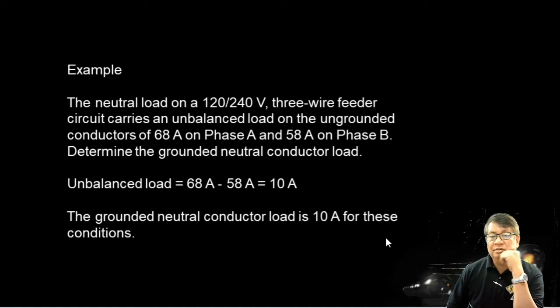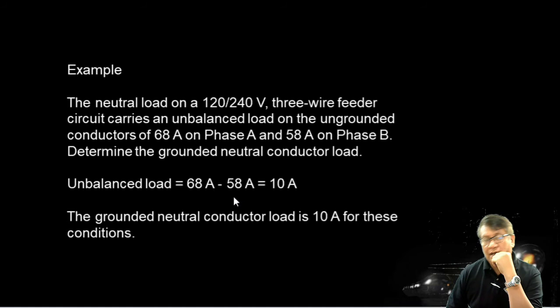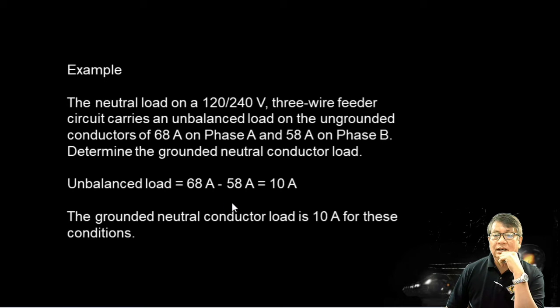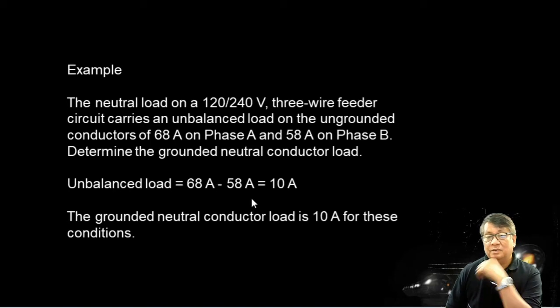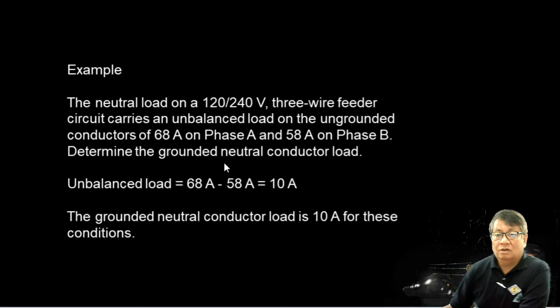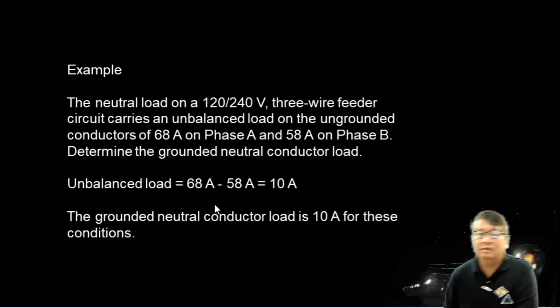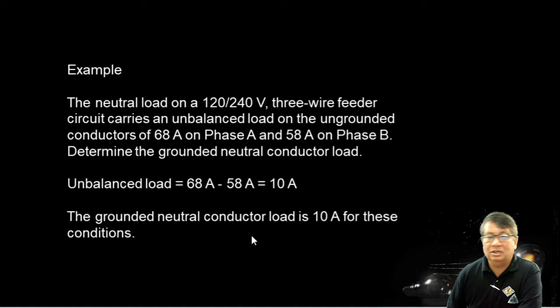So unbalanced load means the result of subtracting the full load and the no load, the 68 amperes. So we have here the ungrounded, and then we have this minus 58 amperes, no? So for phase A and phase B respectively. What you're going to do to determine the unbalanced load is subtract 68 by 58, and we have here already 10 amperes. So the grounded neutral conductor used is 10 ampere for this condition.